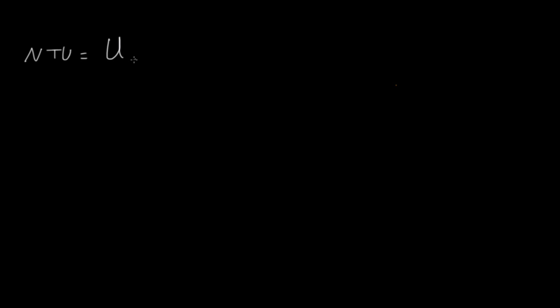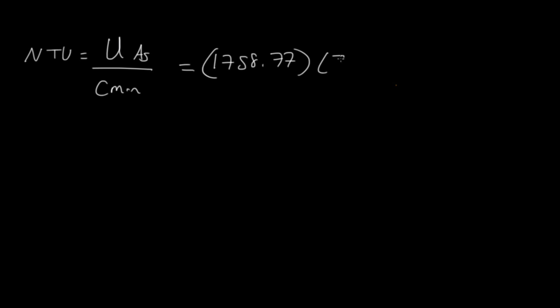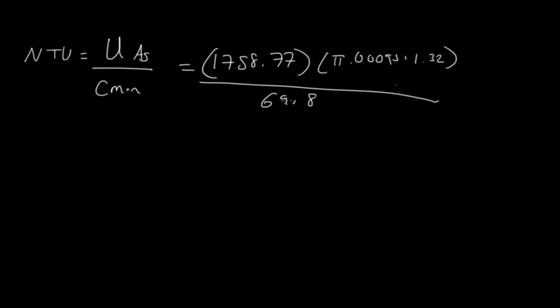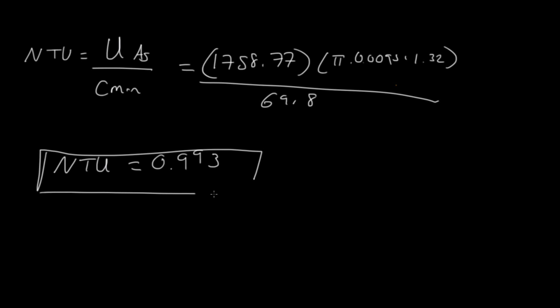The last thing we need to find is the number of transfer units (NTU), which equals U × A / C_min. NTU = 1758.77 × (π × 0.0095 × 1.32) / 69.8 = 0.993. That is our number of transfer units — the third answer.